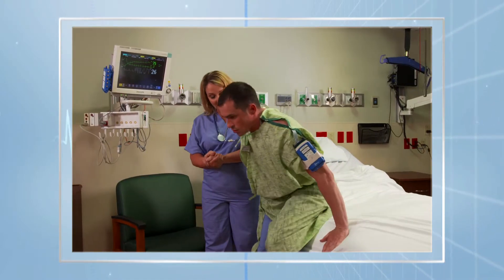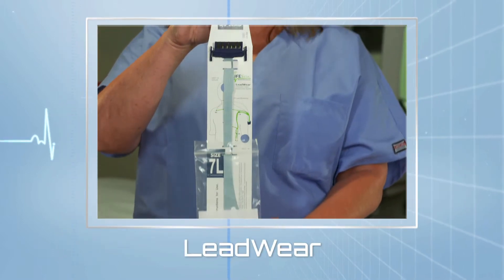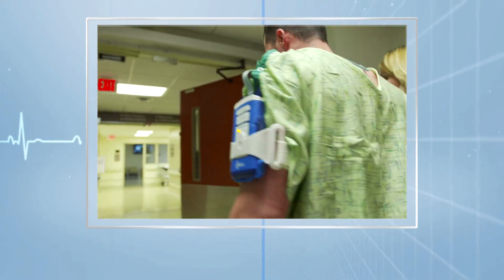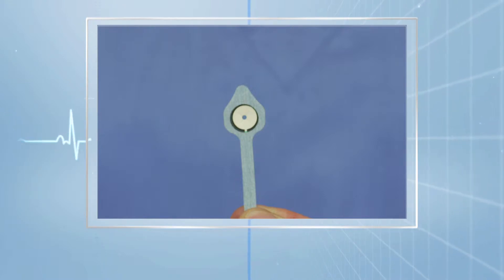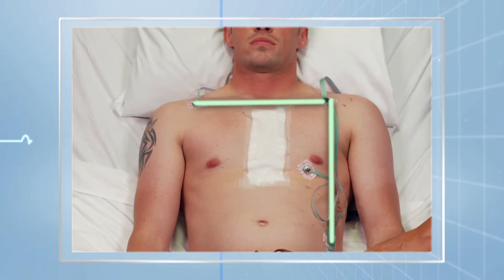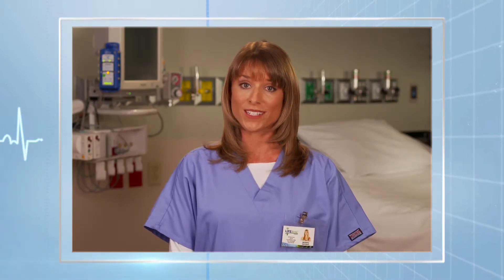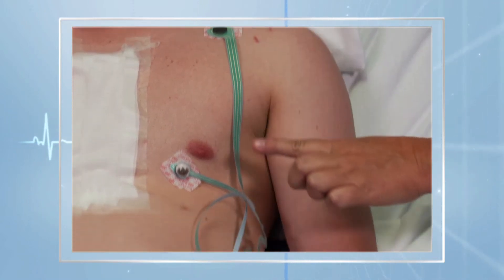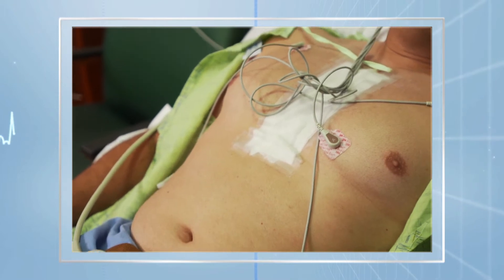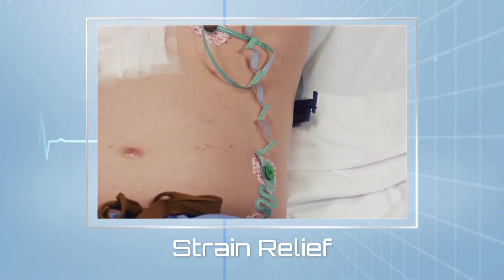The high-technology LifeSync Bluetooth wireless platform is paired with a unique ECG lead wire design called Leadware. Many of the benefits gained from using the LifeSync system come from several unique design elements of the Leadware. The Leadware is a single-patient use design which remains on the patient throughout their hospital stay. It is extremely lightweight and the patient-facing side is covered for maximum patient comfort. The Leadware is designed like the number 7, with the top of the 7 placed behind or optionally in front of the neck with standard lead placement for right arm, left arm, and down the left side of the body to the left leg. Sternum and pocket incision areas are kept clear. The LifeSync Leadware incorporates a strain relief feature so that patient movement doesn't pull on the electrode or pull the electrode attachment from the Leadware.